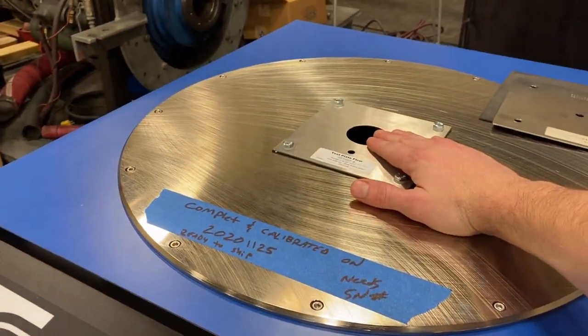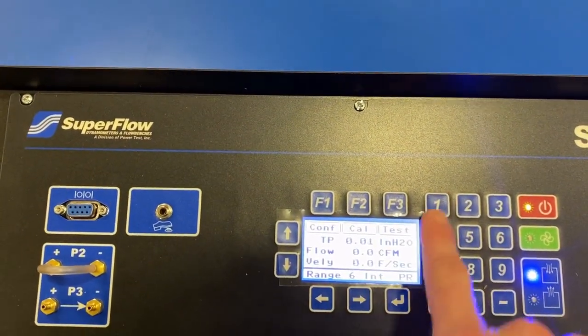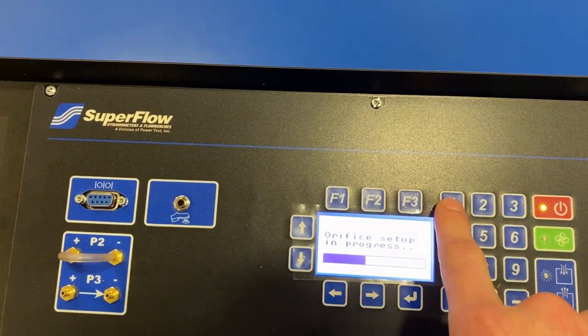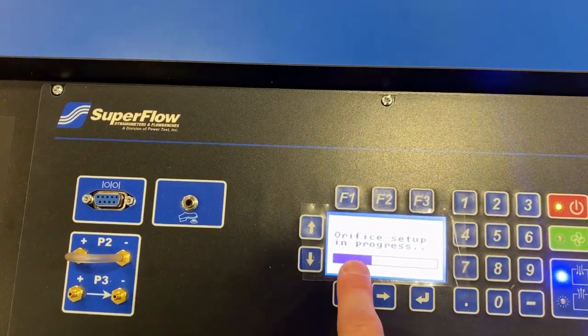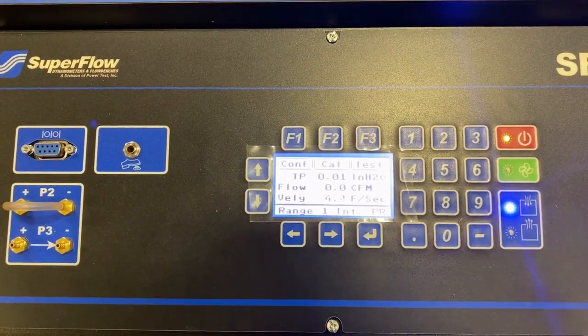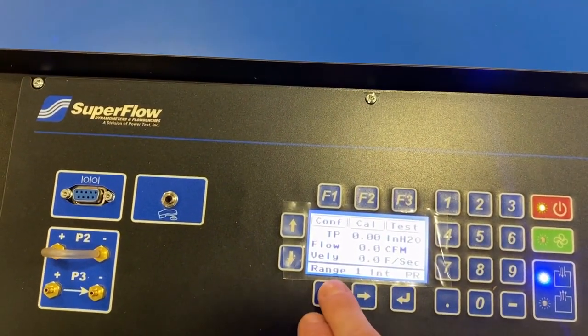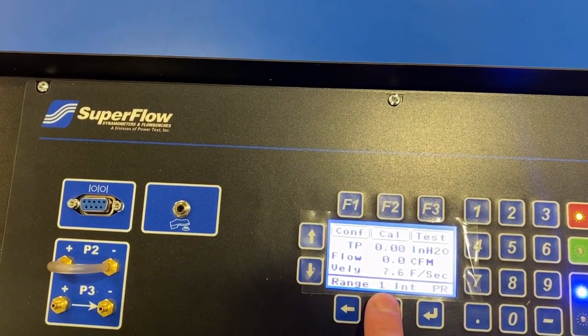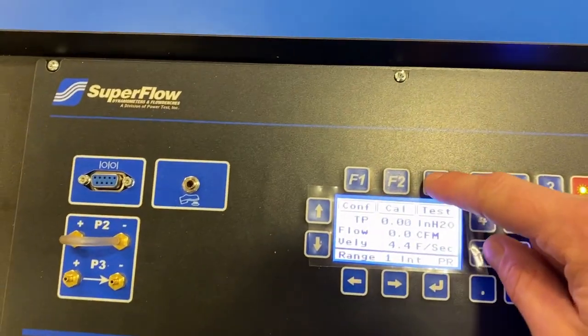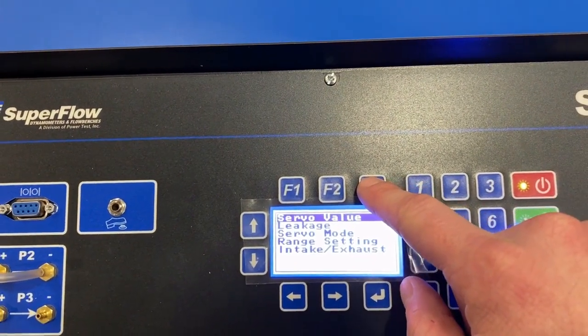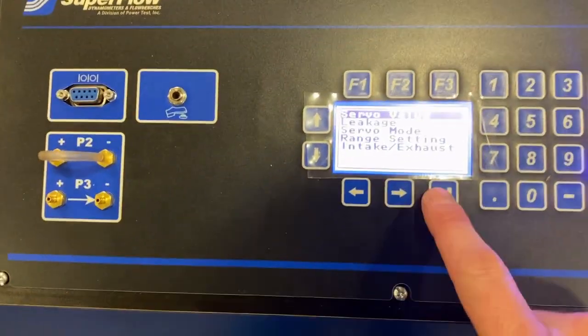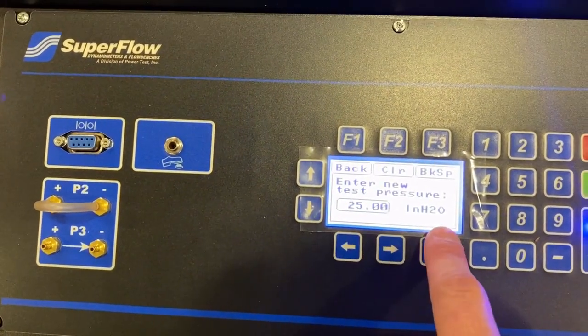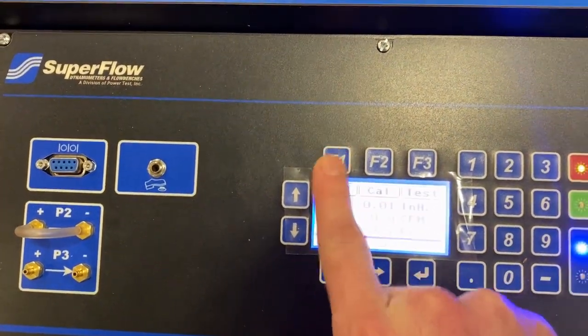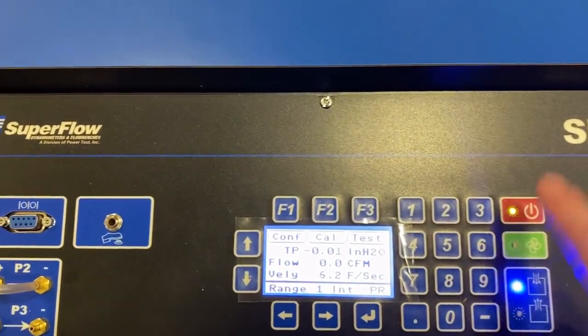In order to verify leakage, we would plug the hole with the rubber stop and then flow the bench in range 1. So we just have to press 1, it'll change the range. Once the orifice setup range is set to 1, we're going to set the test pressure to 25 inches of water. And we would hit flow. We would hit the fan button, it would begin to flow.